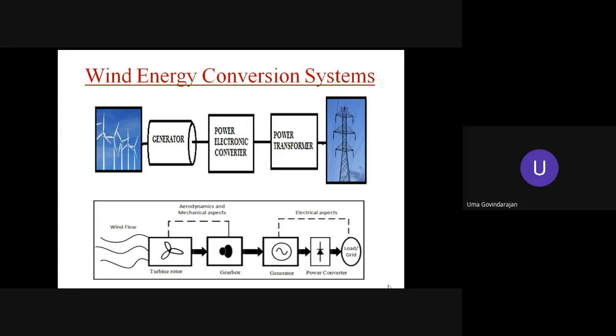I'm not going into the details in the beginning. It is only an illustrative block diagram of how energy conversion is carried out. From the wind turbine, the shaft of the wind turbine is connected to the generator. Then the generated power is conditioned using a power electronic converter. From the power electronic converter, to suit the transmission voltage levels, we have different types of power electronic converters available, and different power transformers are available. This power transformer acts as a pooling station which collects power from different wind turbines. Then the output of the power transformer is connected to either an HV line or the transmission line.